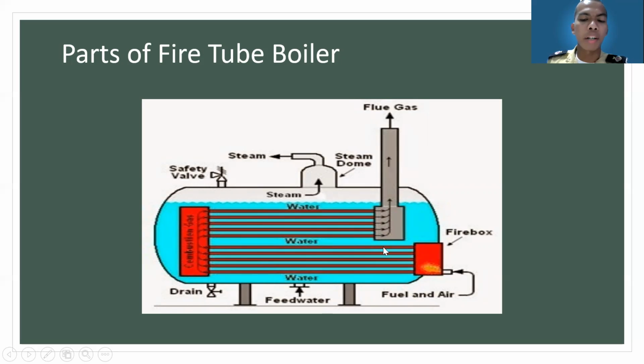And also the feed check valve. Feed water enters the boiler through the feed check valve, which also stops the feed water from returning, and it is used as a non-return valve. To increase the efficiency of the boiler, the following accessories are provided: the economizer, the air preheater, and also the superheater. The efficiency of the boiler will be low if operated without the accessories.